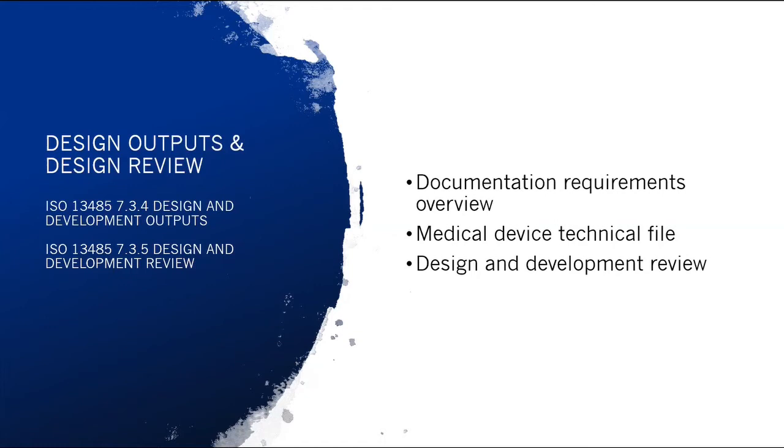They are not only the functioning working device and the hardware designs and software designs, but all of the documentation that goes with that, including the design descriptive documents, the planning and protocols required for verification, testing, validation, etc. All of these documents ultimately go into what's called the medical device technical file, which is the technical document compendium. It then itself becomes a part of the medical device file, which includes not only the technical documents, but verification and validation reports and risk management reports and all sorts of other documentary artifacts.